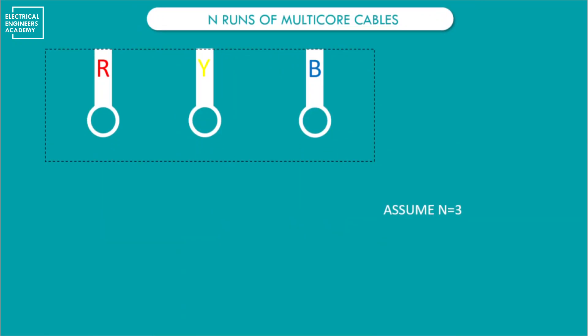To start with, we have two cases — let's limit it to two cases for the sake of simplicity. The first case is n runs of multi-core cables. Our load is connected using n runs, which can be any number — one, two, three, etc. — and represents the number of cable runs connecting our load. The second case involves single-core cables, which is the main source of confusion for many engineers, both experienced and new.